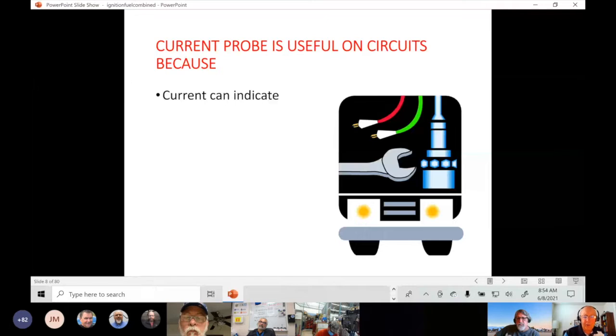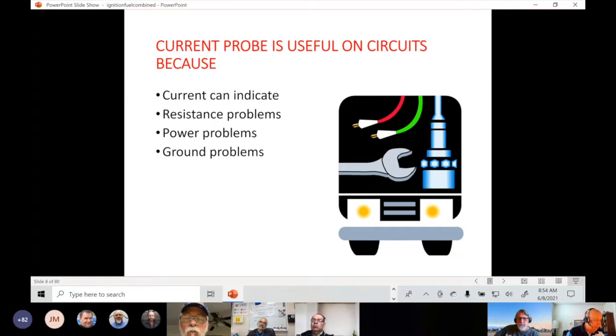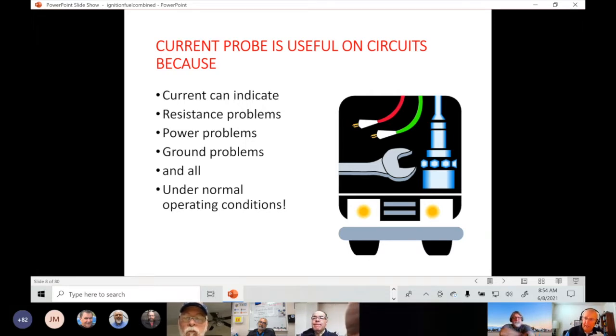So why do we want to use a current probe? A current probe reveals resistance problems, power problems, and ground problems, and the big key is they're all found under normal operating conditions. So the key here is we're not disconnecting anything.